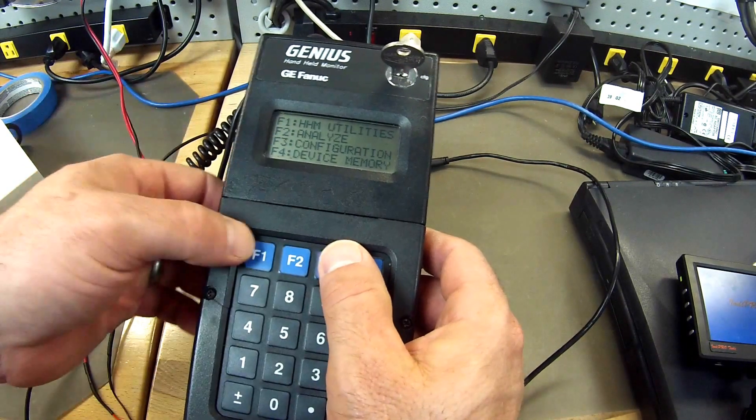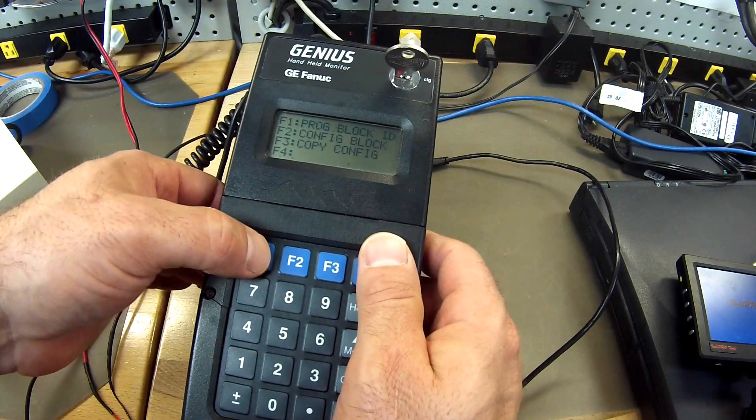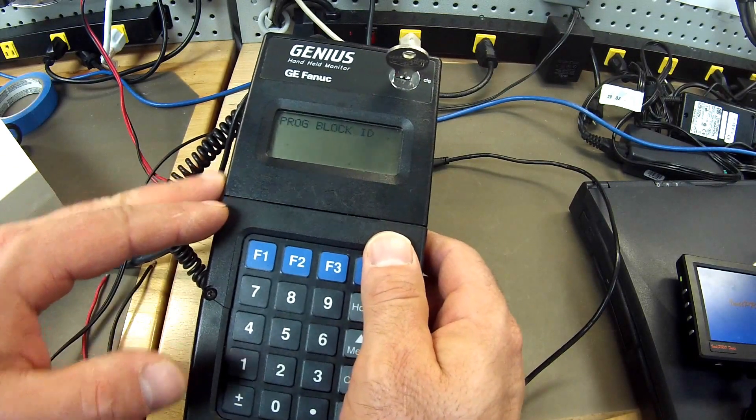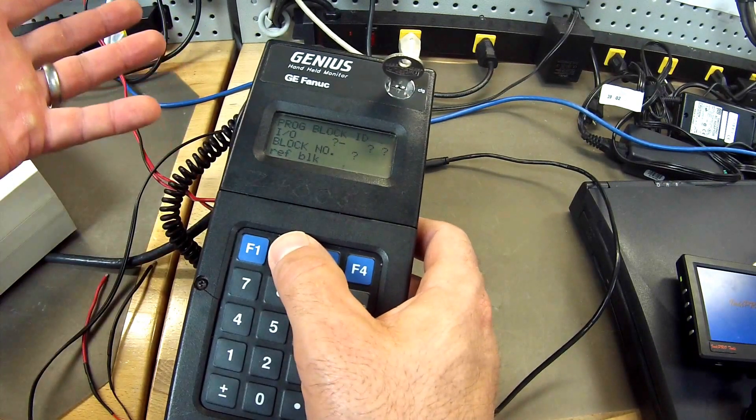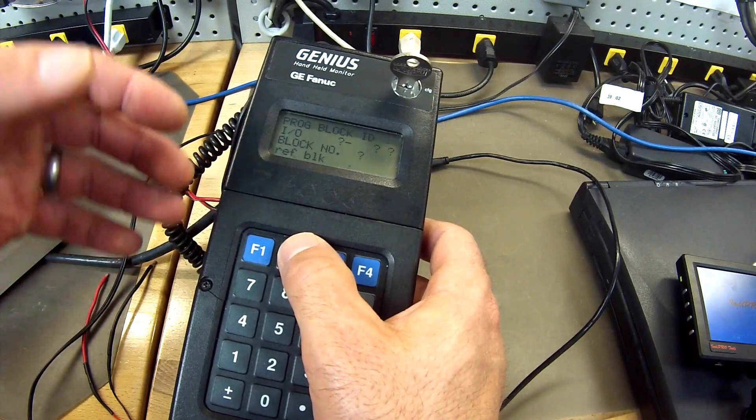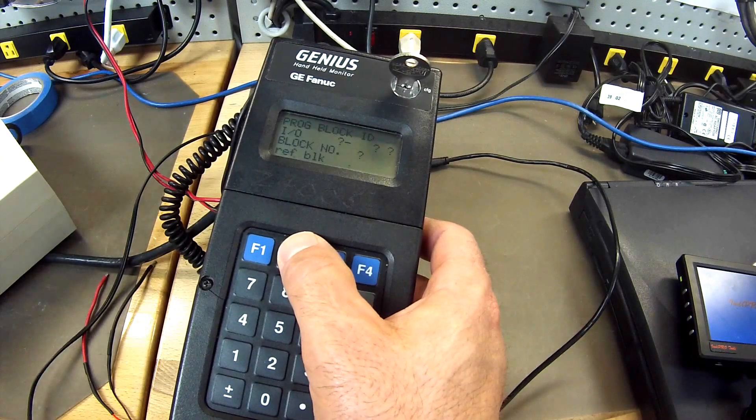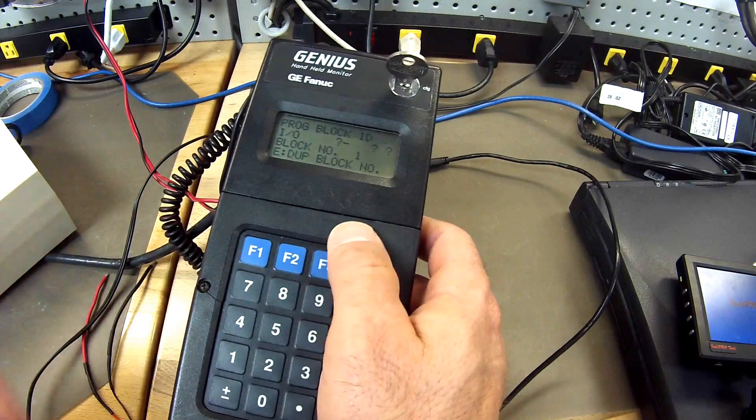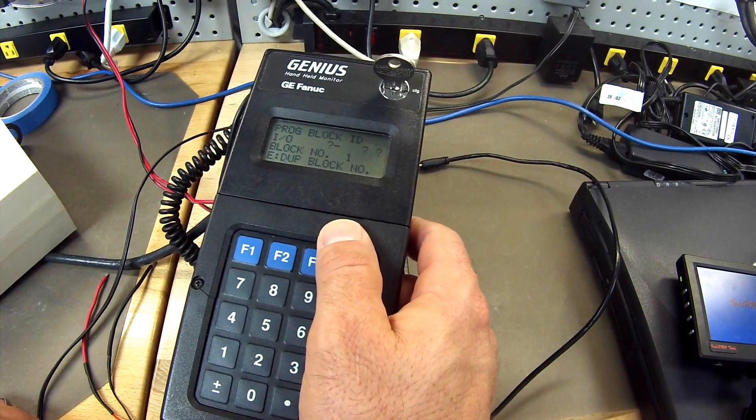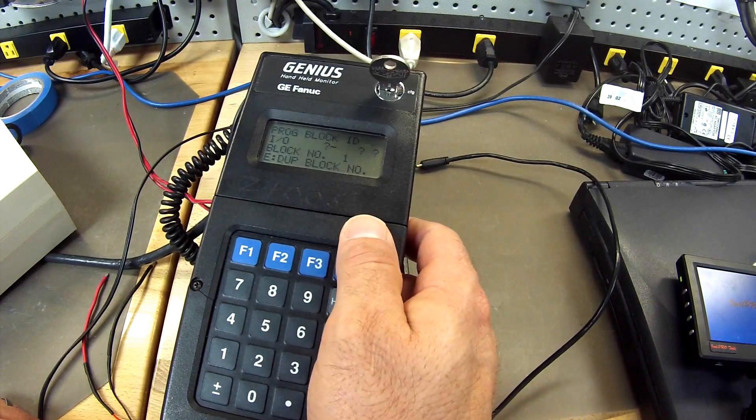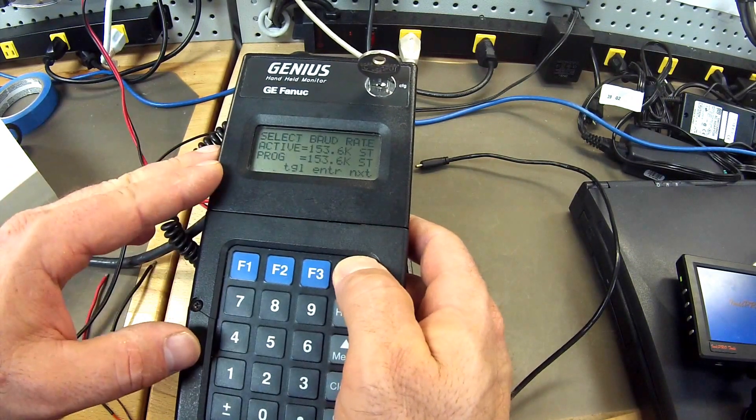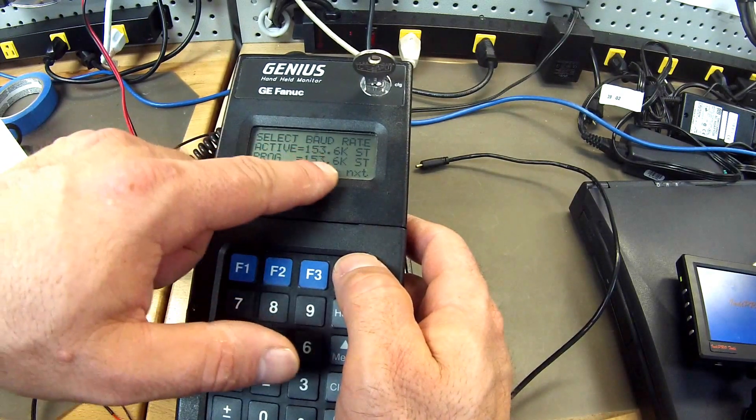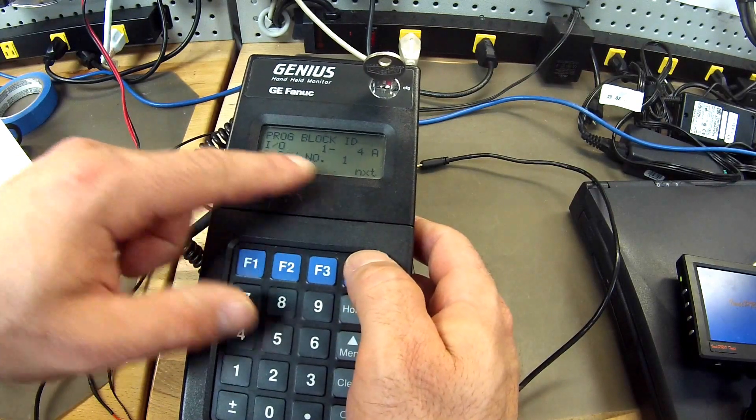Next thing I want to do is go into my configuration, F3, and program my block ID. For my test sake I want to make sure that the block number matches what I have in Proficy Machine Edition. And just for a simple test I am going to call it block number one. So I have block number one. And then again I am going to check, I hit next, and I am going to check my baud rate is standard like I mentioned before. That is very important. So block number one.